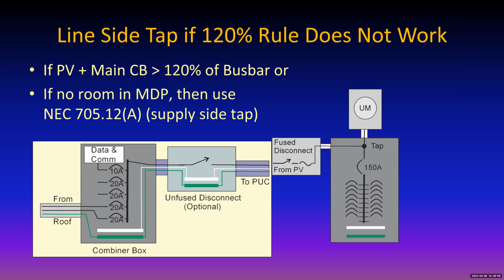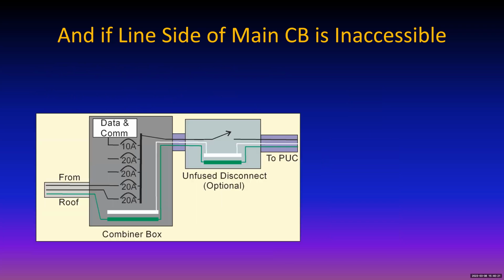But here is your line side tap. Pretty straightforward. You just connect in, and as long as your PV does not exceed the rating of that feeder from the meter down to the distribution panel, you're good. So that's another way to do it. But sometimes you can't get to that line side of the main circuit breaker. So then what are you going to do?